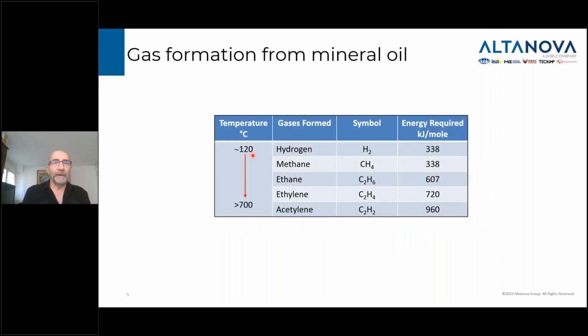Now, why are those gases created? Well, as the temperature of the fault increases, as I said, from 120 to way over 700 degrees C, and up to 1200 for acetylene, the fault generates a lot of energy, and that energy creates those gases. So if you start seeing methane in your DGA, methane carries mostly around 338 kilojoules per mole of energy. Acetylene requires 3 times more energy to be created. And this is why people are much more worried when they start seeing, especially, ethylene and acetylene, because those two gases carry a lot of energy, plus the hydrogen that's also generated.